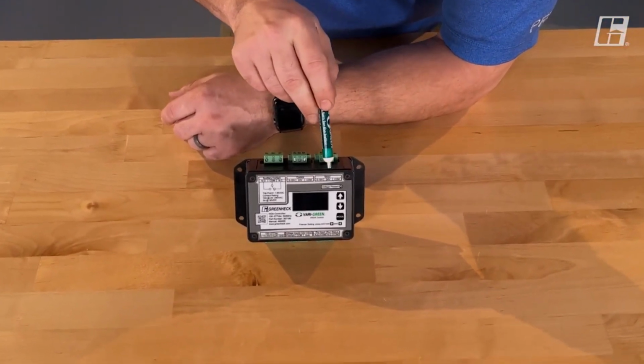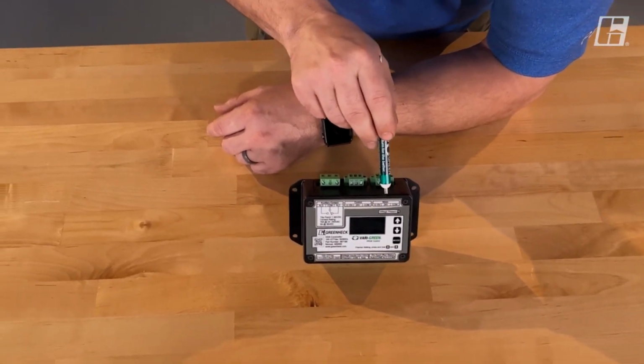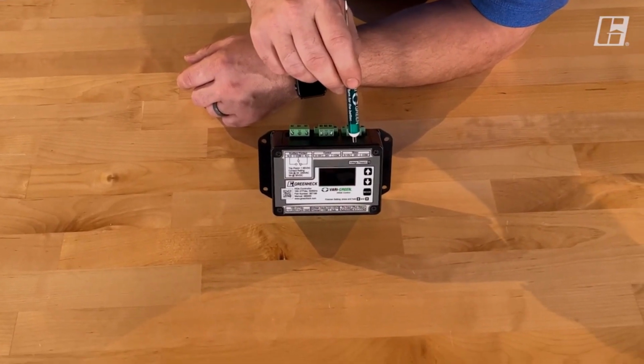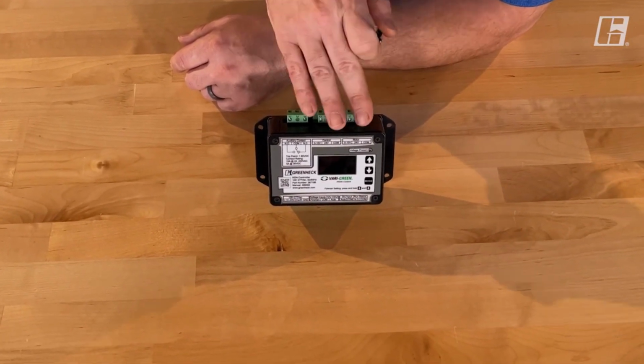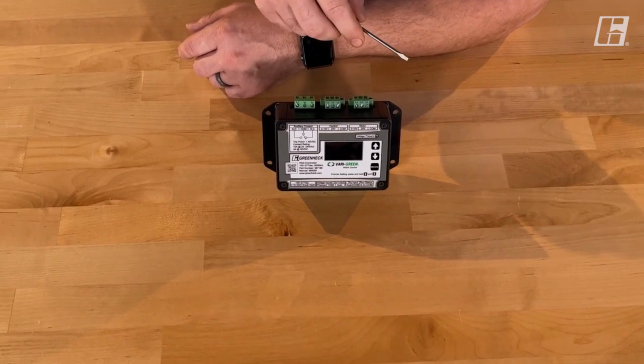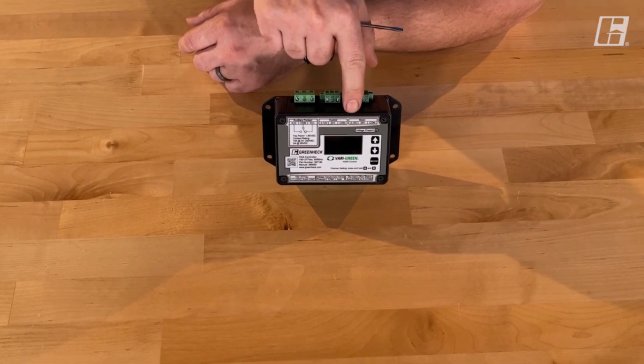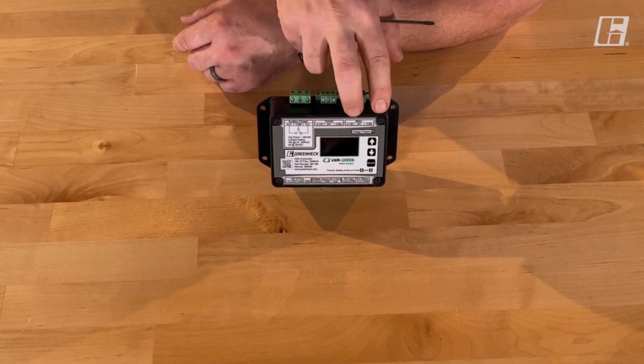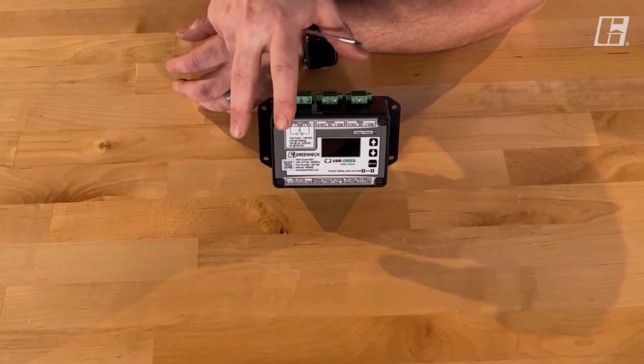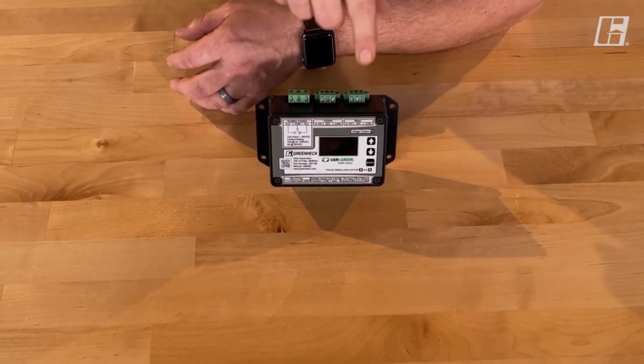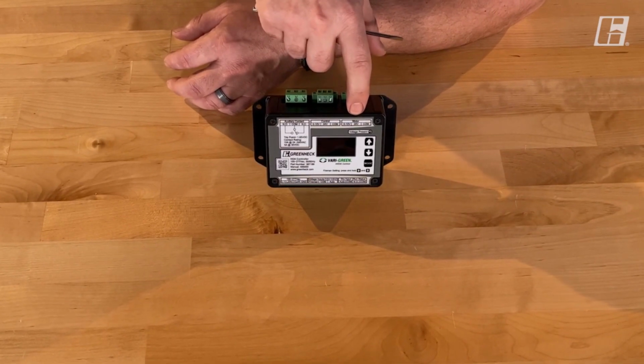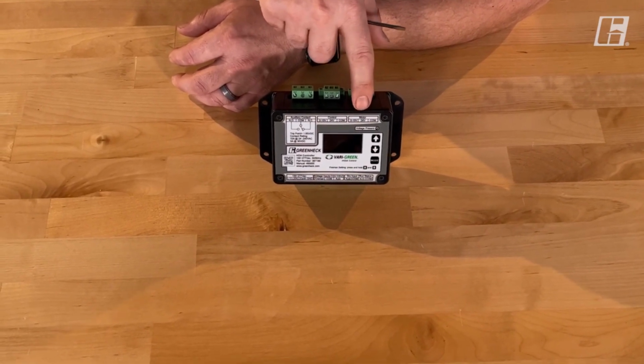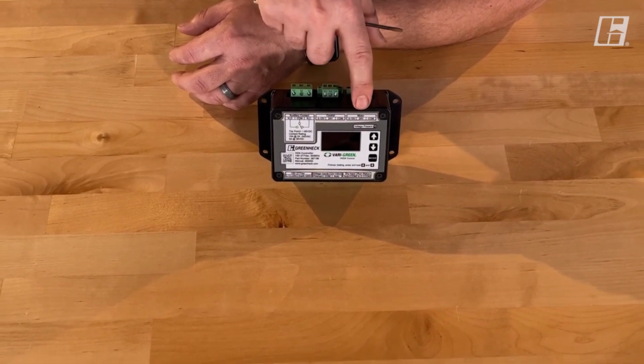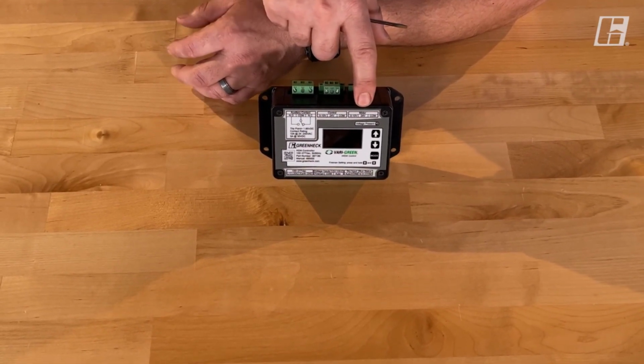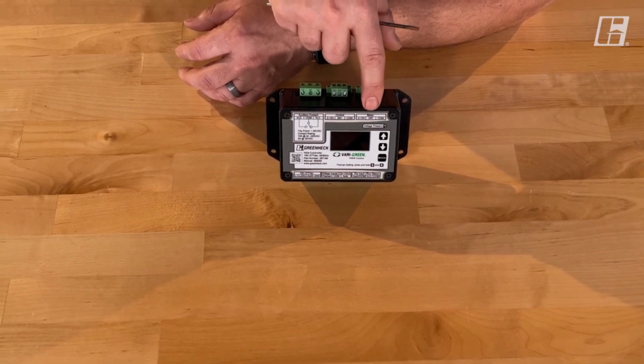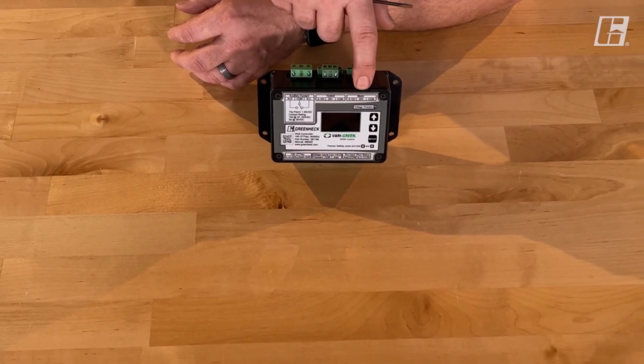The first terminal we're looking at right here is labeled motor. This is where our 2-wire is going to be wired from this device to the motor itself, and we're only going to use common and 0 to 10 volt. So this is sending the speed reference from the HOA to the motor. There is a 24 volt output terminal here, and this is kind of a leftover or a legacy item from earlier generations of Vari-Green motors. So you'll typically not see a wire used in the 24.